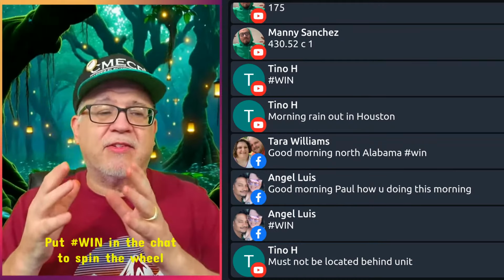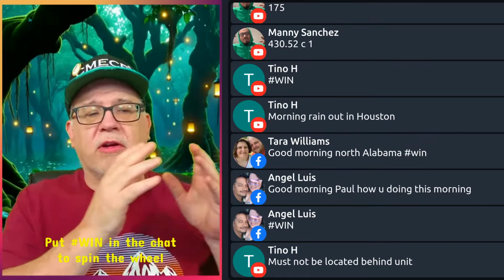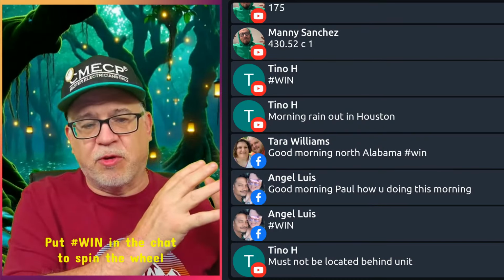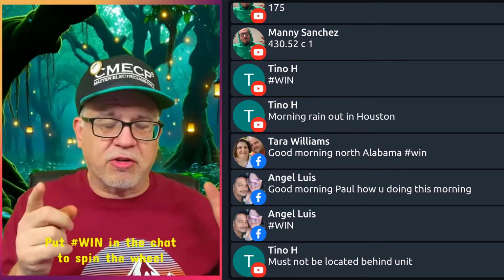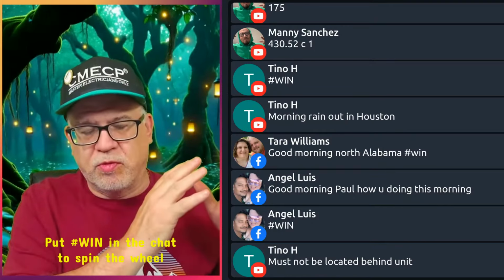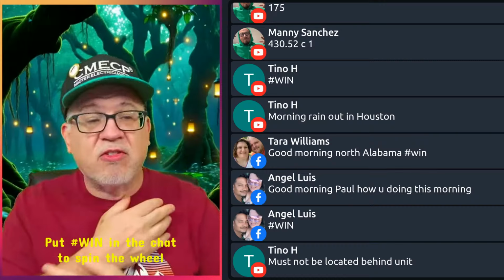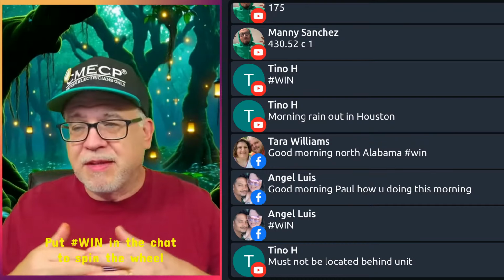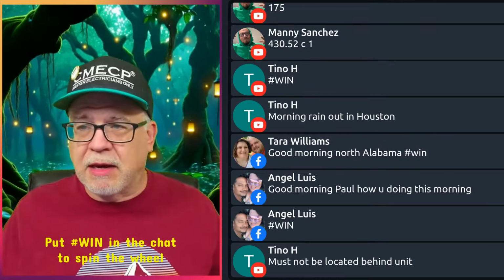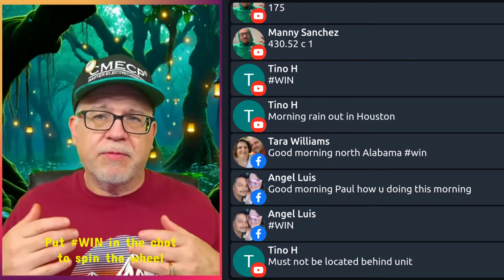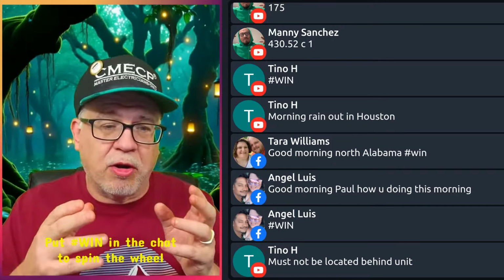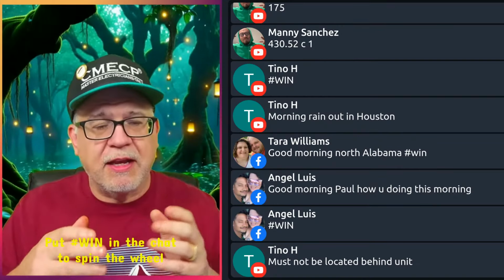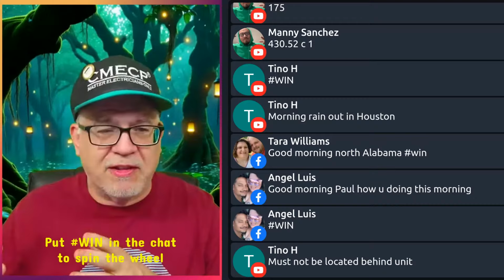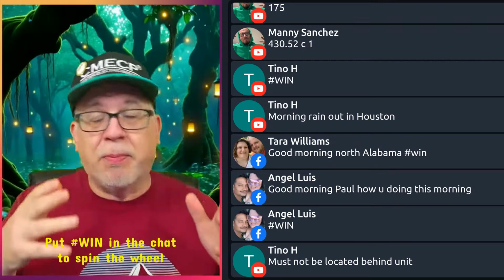Well, that is when that disconnect becomes a junction box and you're going to end up having to move a disconnect further down and then reroute your conductors in order to get the disconnect further so that it has its working clearance. It sucks. It is what it is. It's the chicken or the egg. A lot of people will poke out their wire or their cable where they're going to put their disconnect, and then the HVAC folks come and set that unit. And they might still put it in front of the cable.